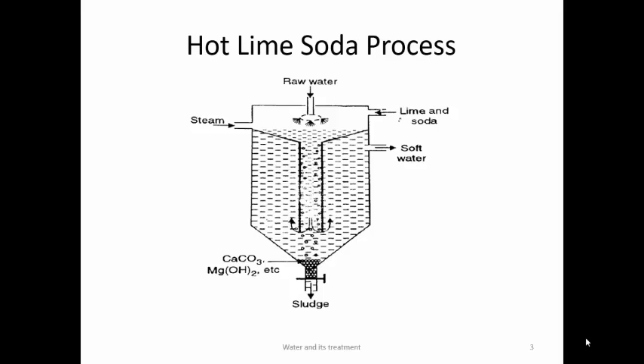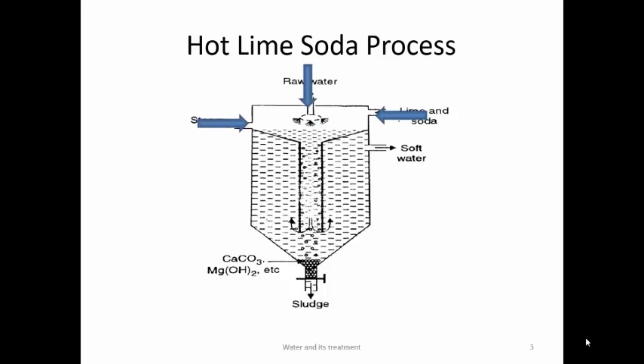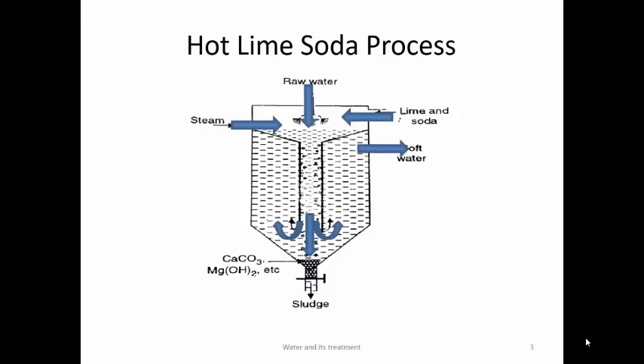All shortcomings of the cold lime-soda method are overcome in the hot lime-soda process. It consists of three parts: conical sedimentation tank, reaction chamber, and a wood fiber filter. Raw water is taken from one inlet, lime and soda from another, and high-pressure steam from a third inlet. The reaction is carried out at around 80–120°C. The sludge settles at the bottom and is removed; soft water rises and is removed via outlet. No coagulant is needed at high temperature, and the precipitate settles quickly. Residual hardness is 15–30 ppm.